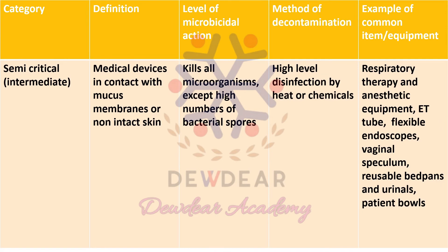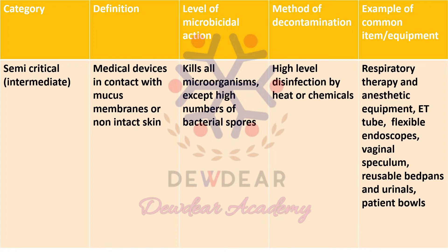The second category is semi-critical, or intermediate. This includes all the medical devices that come in contact with mucous membrane or non-intact skin. The level of microbicidal action needed is to kill all the microorganisms except high numbers of bacterial spores. The method of decontamination required is an intermediate level, that includes high level disinfection by heat or chemicals.